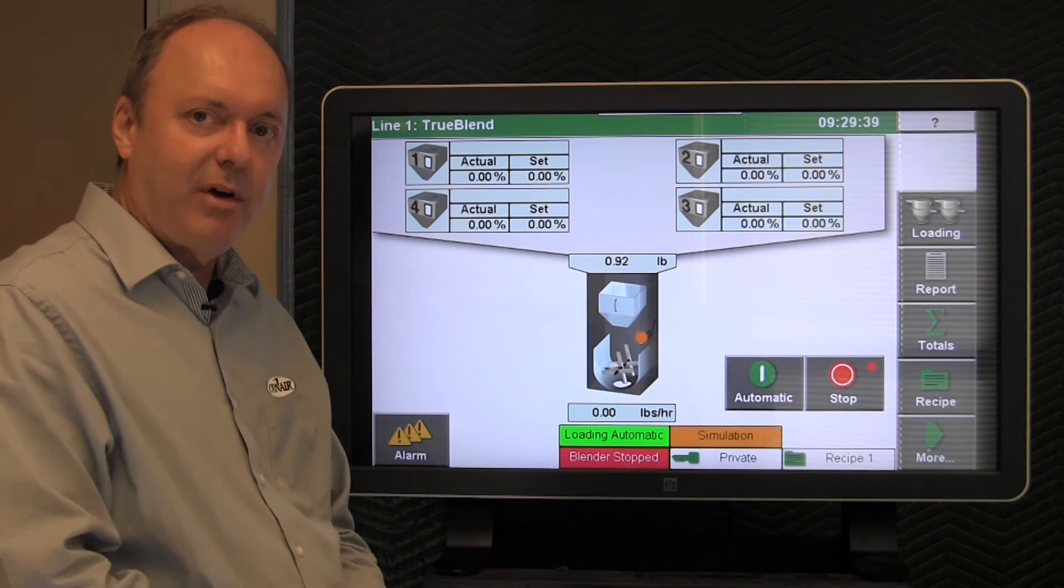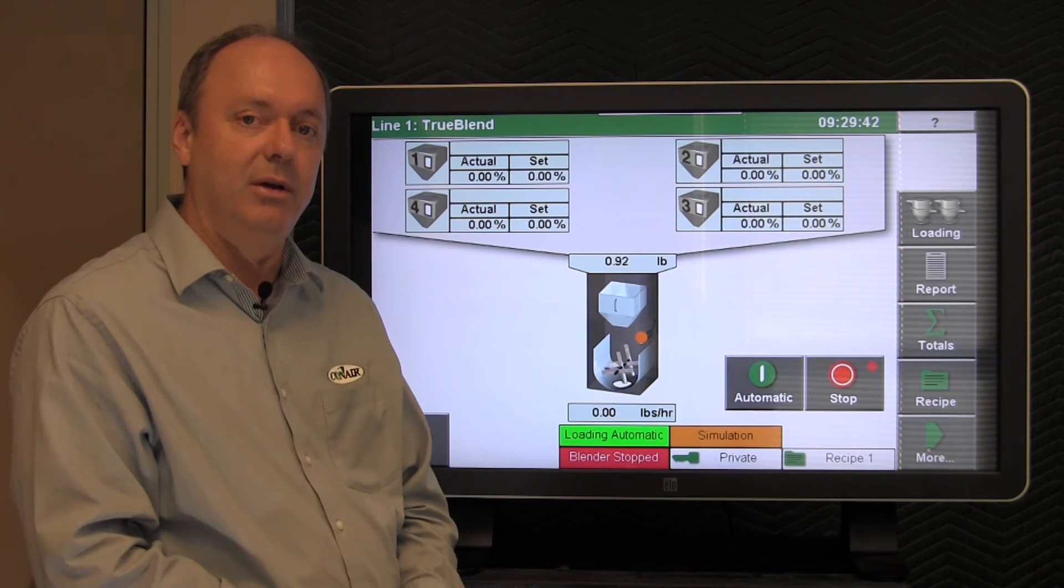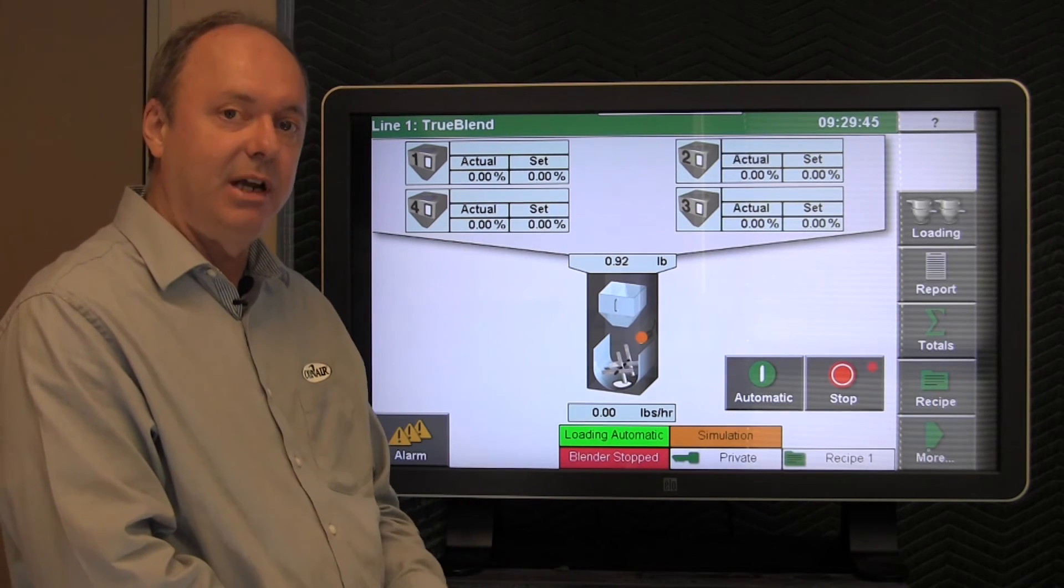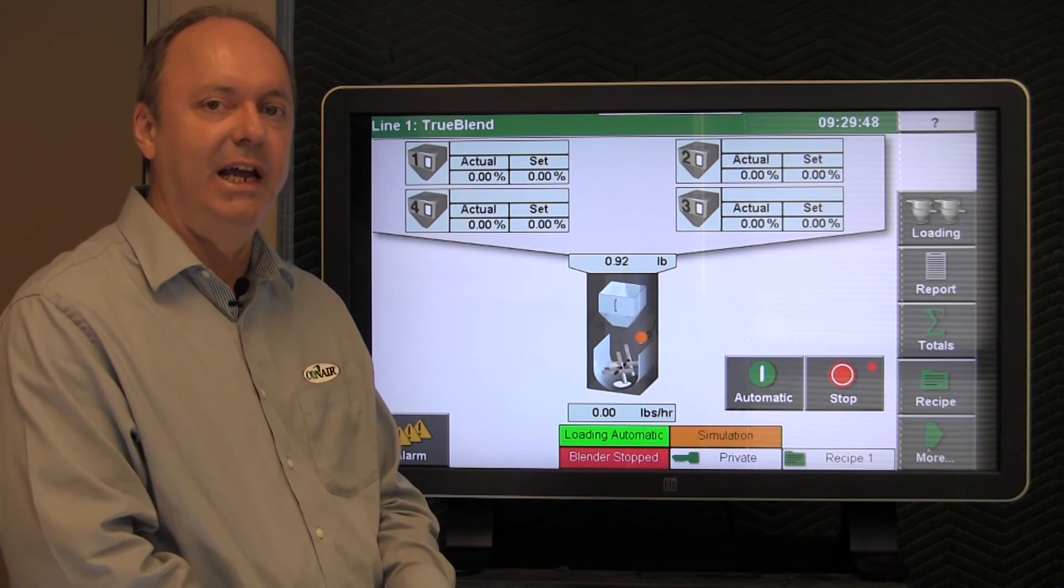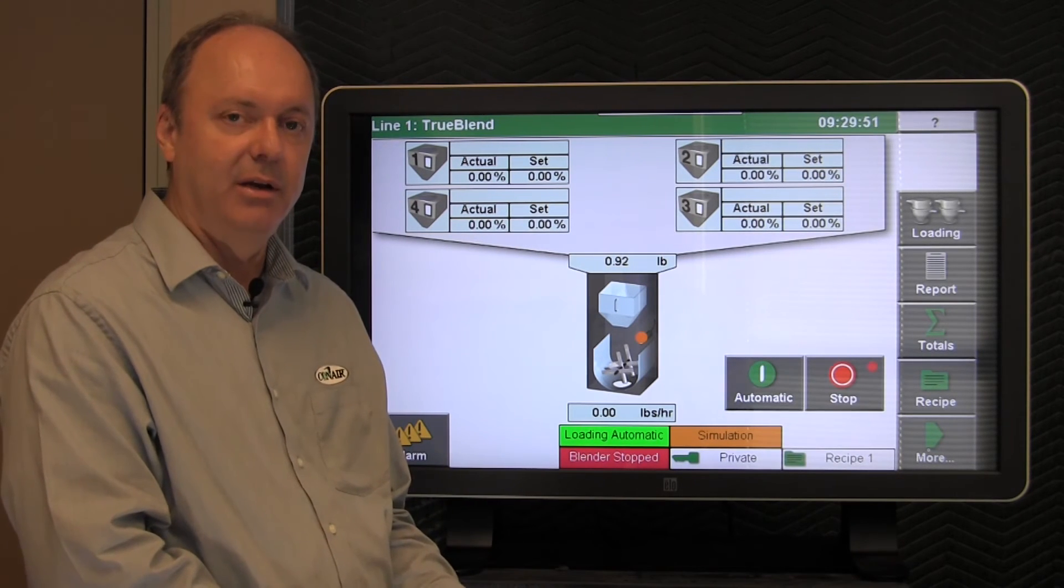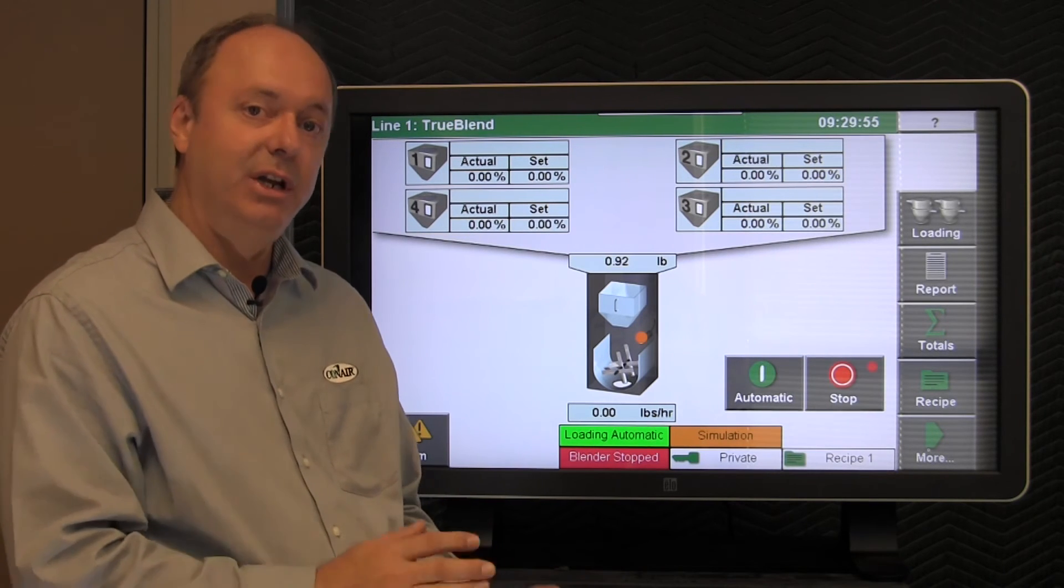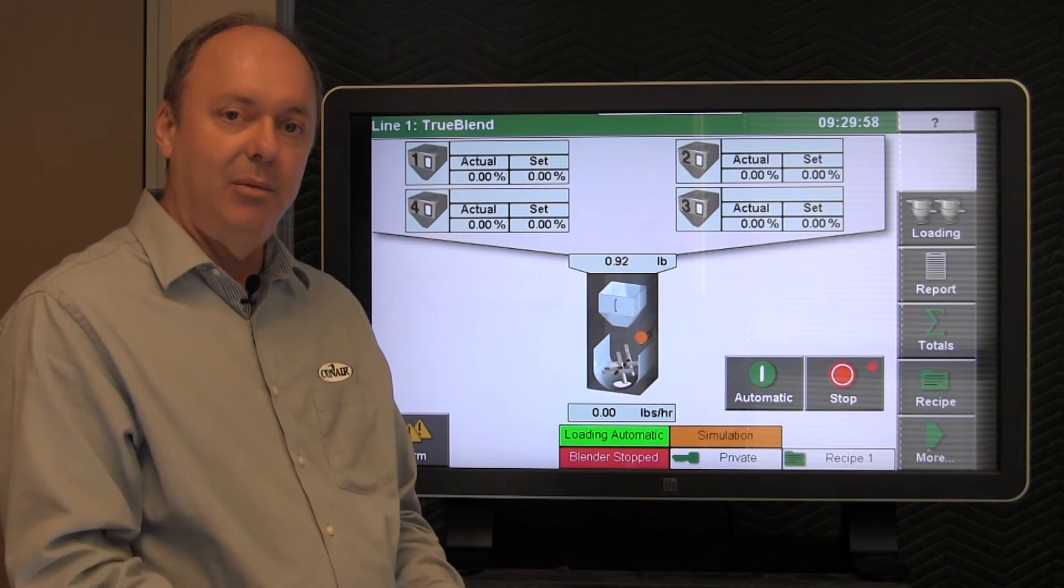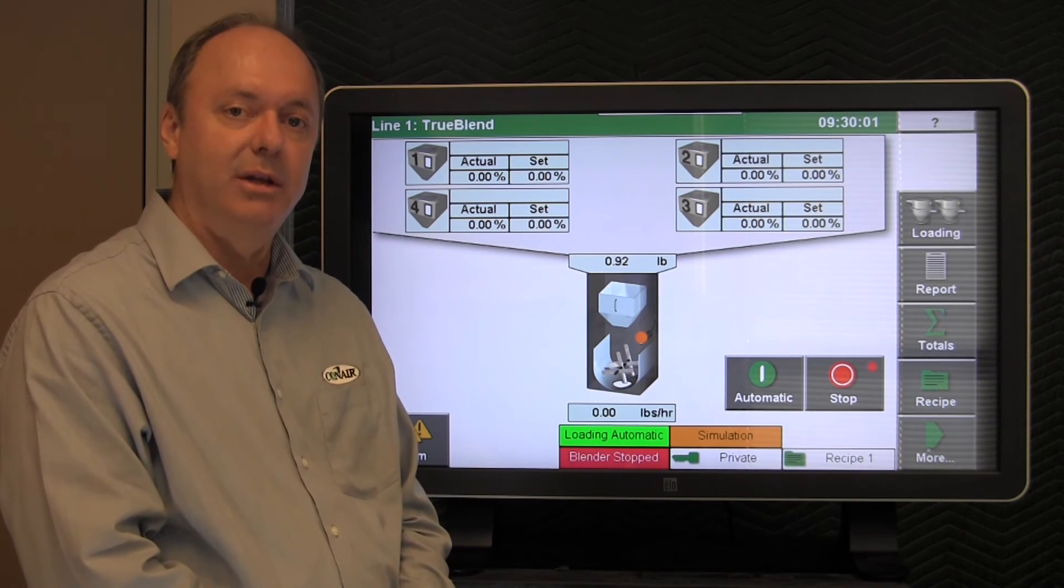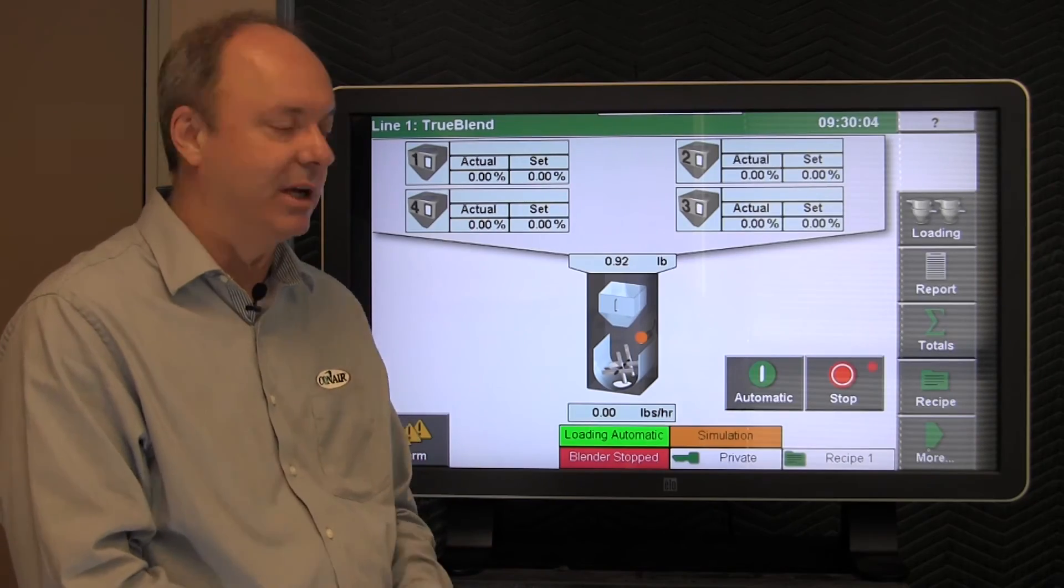If you're unable to find the problem, there is an additional step that you can do that is useful for saving information out of the system. The system will save the last 100 batches that have been created by the blender. All the data associated with that batch, and you can email that to Conair Service Department and we'll analyze it for you in order to help you isolate the problem, whether it's a material problem or a mechanical problem with the blender.